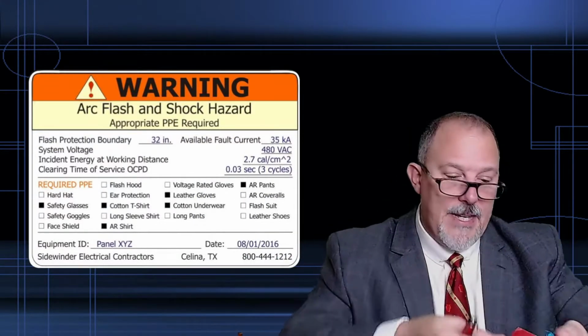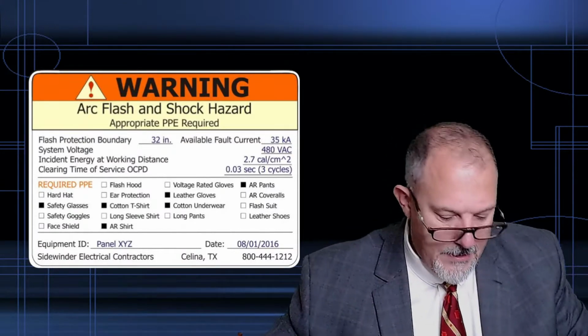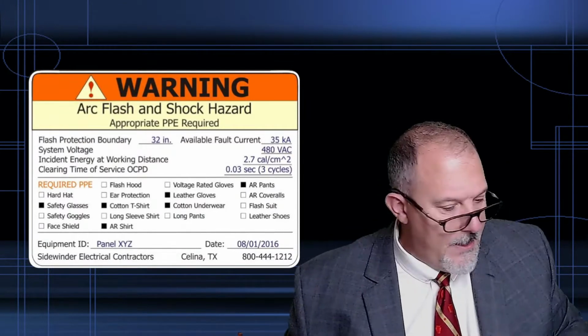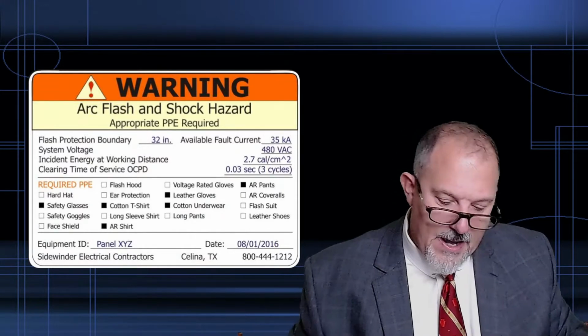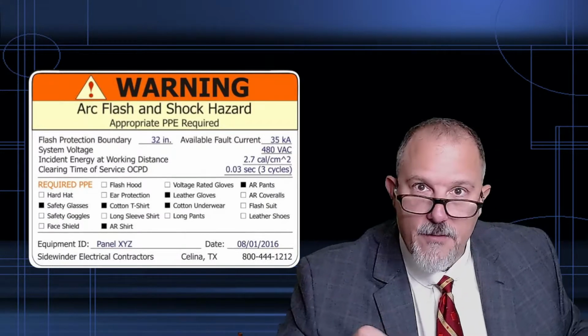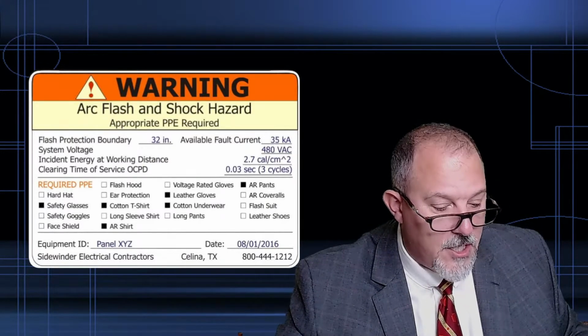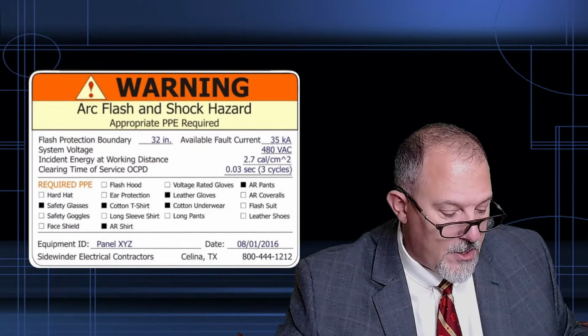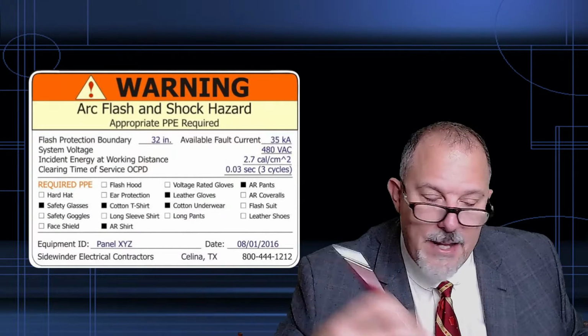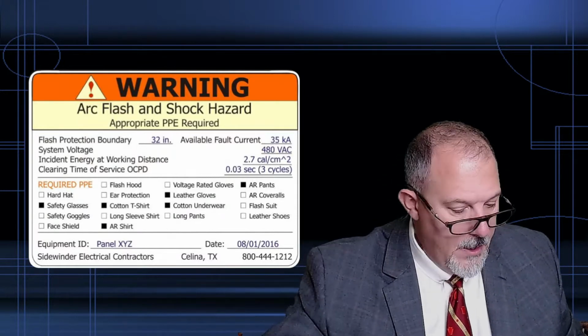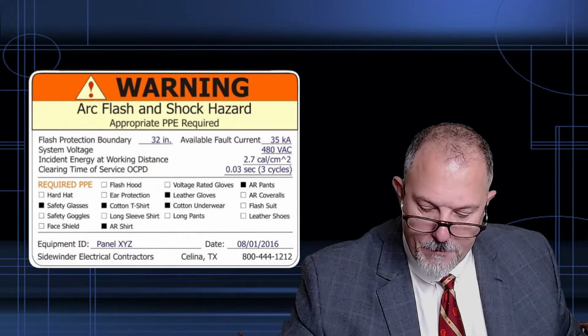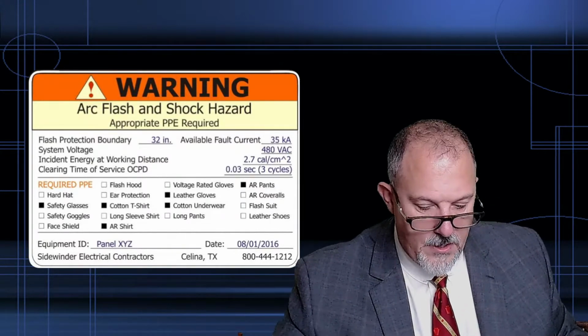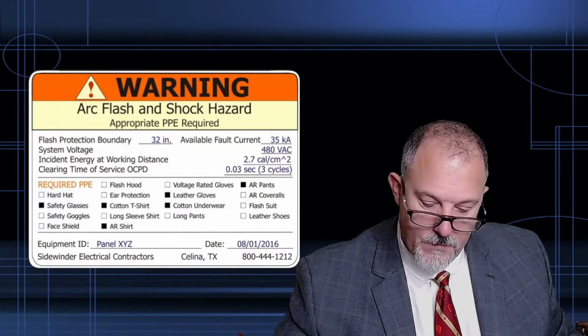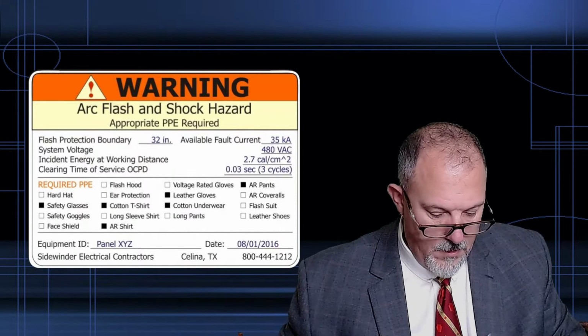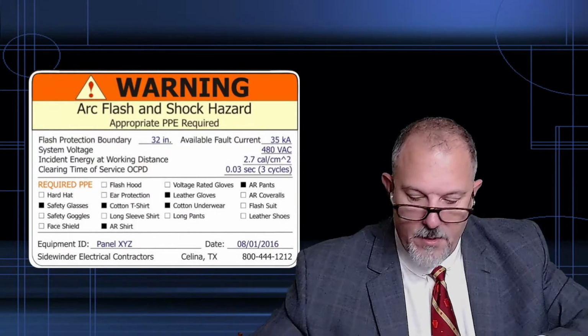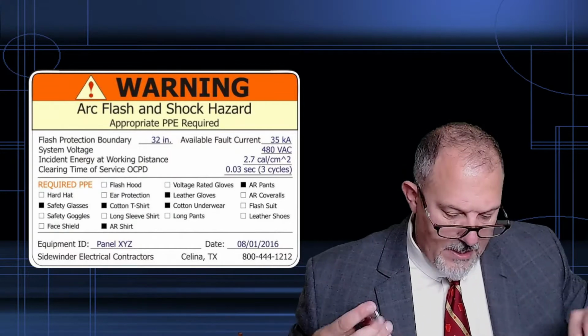And if we go to 70E, oops, caramba. I can't believe I did that. Anyway, 110.5, here we go. Let's talk about hierarchy of risk control. Another thing that this answers. 110.5(H) is the risk assessment procedures. 5 is the hierarchy of risk control methods. 4 is awareness. That's what these labels do, raise awareness. I'm looking for my labels. It's in 130, I believe. 130.5.